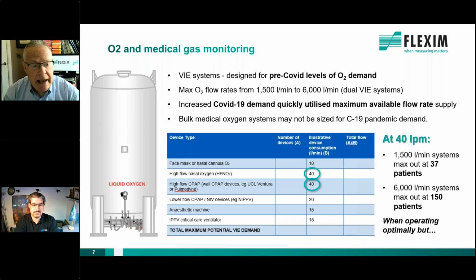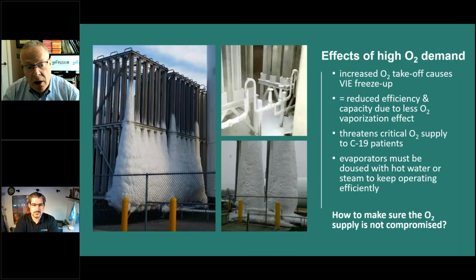But you can clearly see here that in a pandemic the like of which we've never seen before, hospitals were suddenly becoming increasingly worried that their systems were struggling to cope with the demand that was rapidly ramping up. Now, when the system is under full demand, that rapid exchange of liquid to gaseous phase oxygen causes a rapid freezing of the evaporator coils. That equally leads to inefficiency. So those coils have to be doused with hot water or with steam to keep them operating efficiently. And in all respects, this is limiting the capacity of oxygen you can deliver effectively to your critical patients.